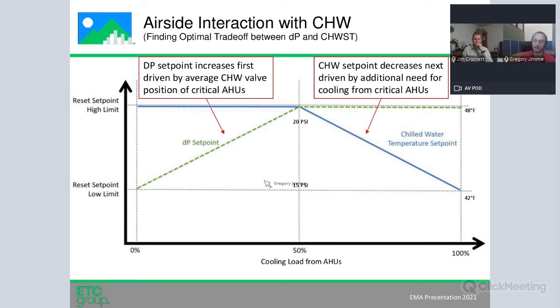So that way you're capturing all of your savings on the chiller first, or as much as you can, and you're paying a pump penalty. But usually it's worthwhile to pay that pump penalty because of the energy saved on the chiller. Again, chiller compressor energy is by far the largest consumer.